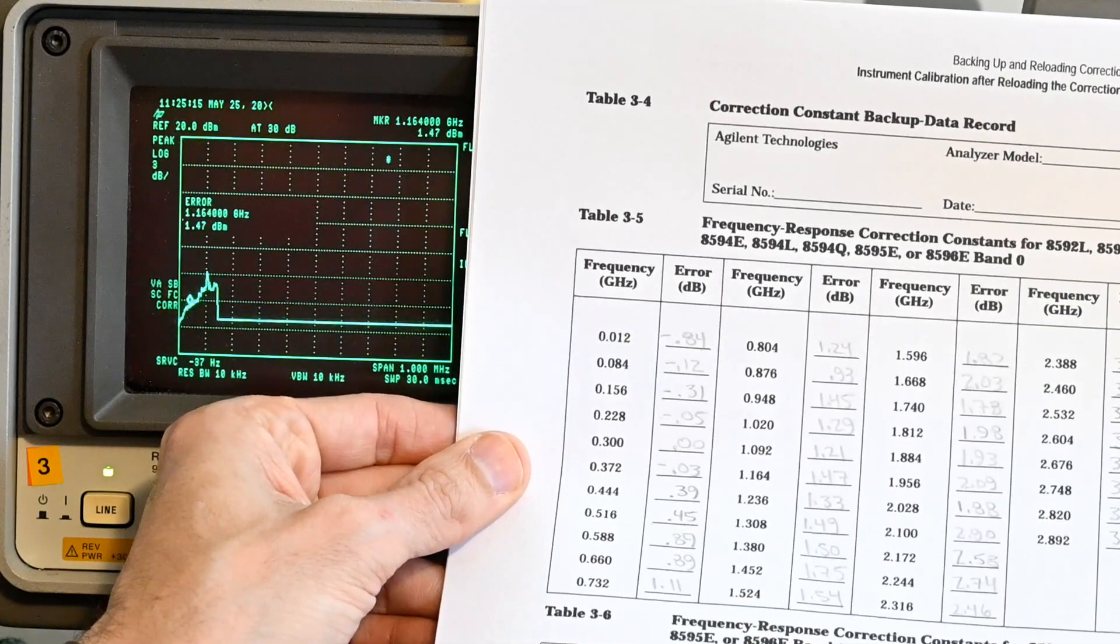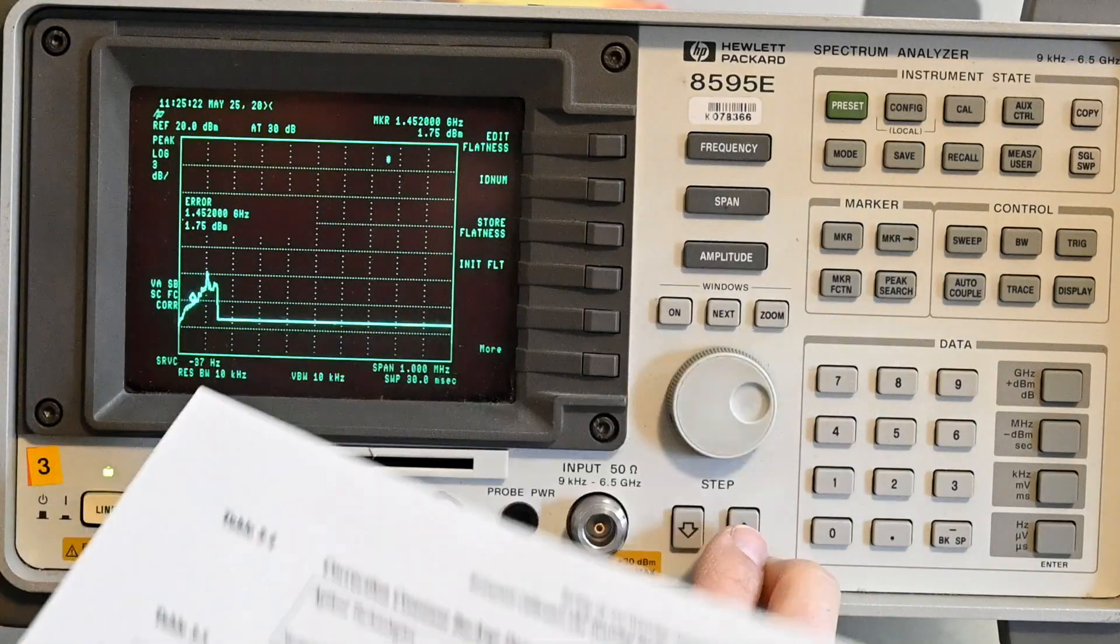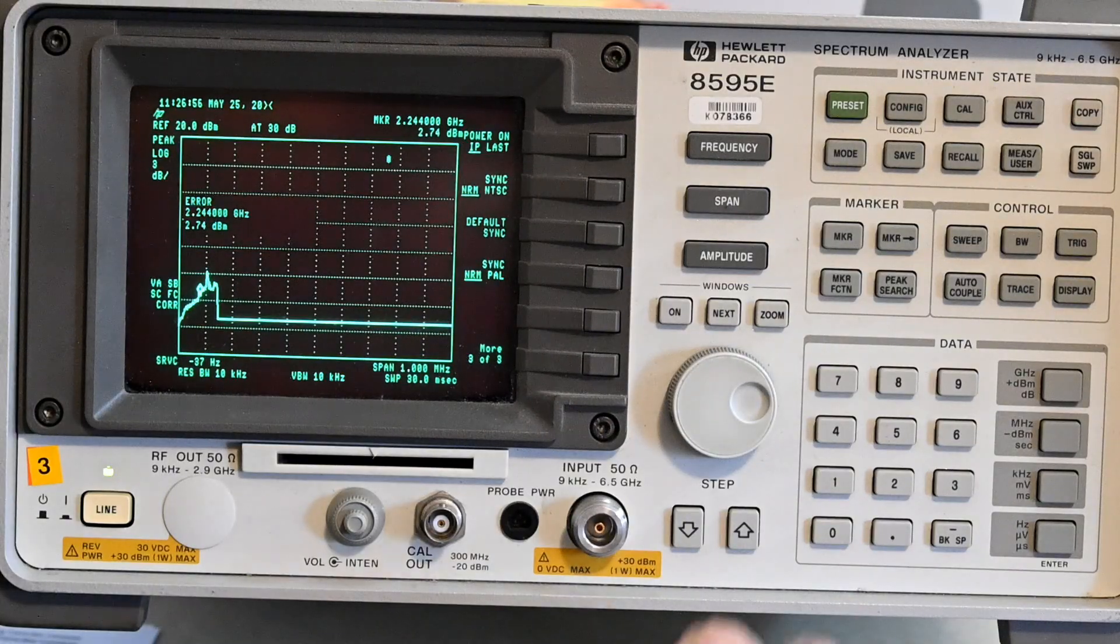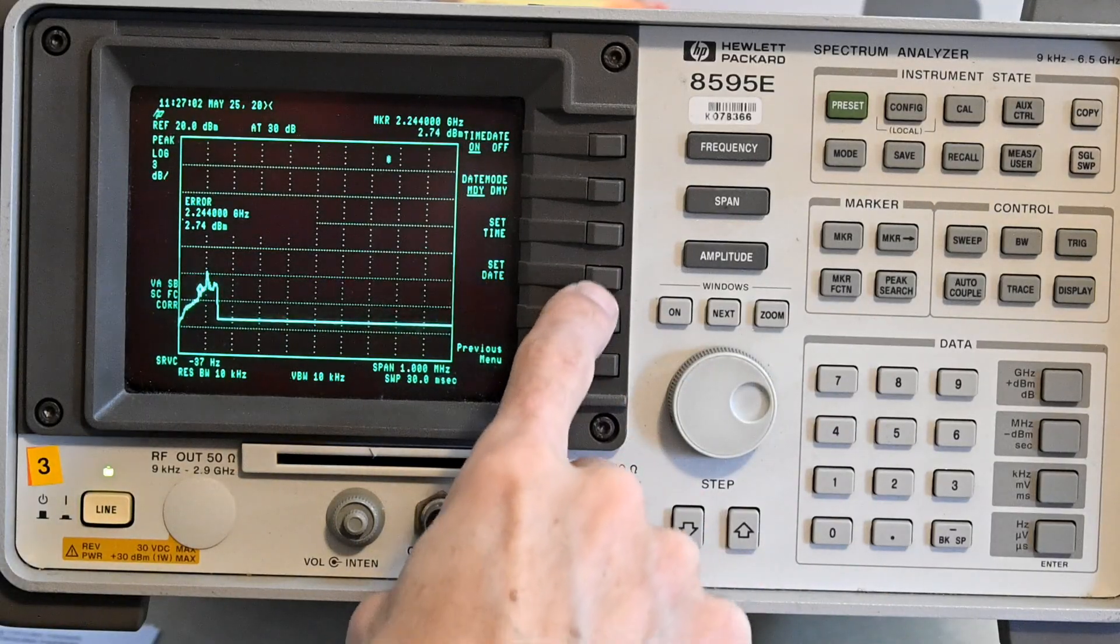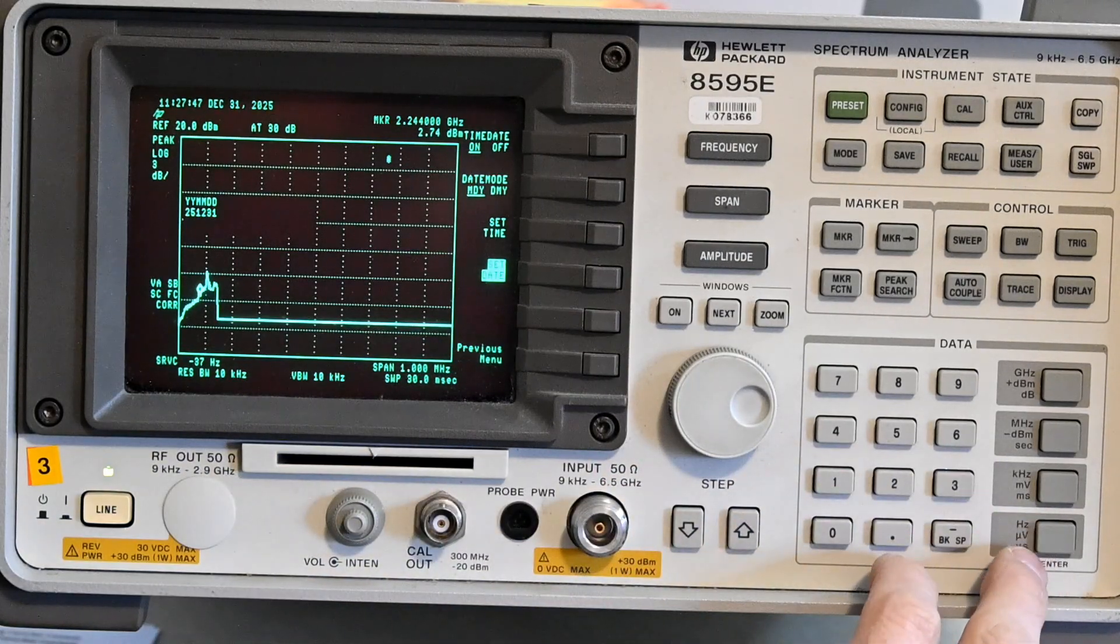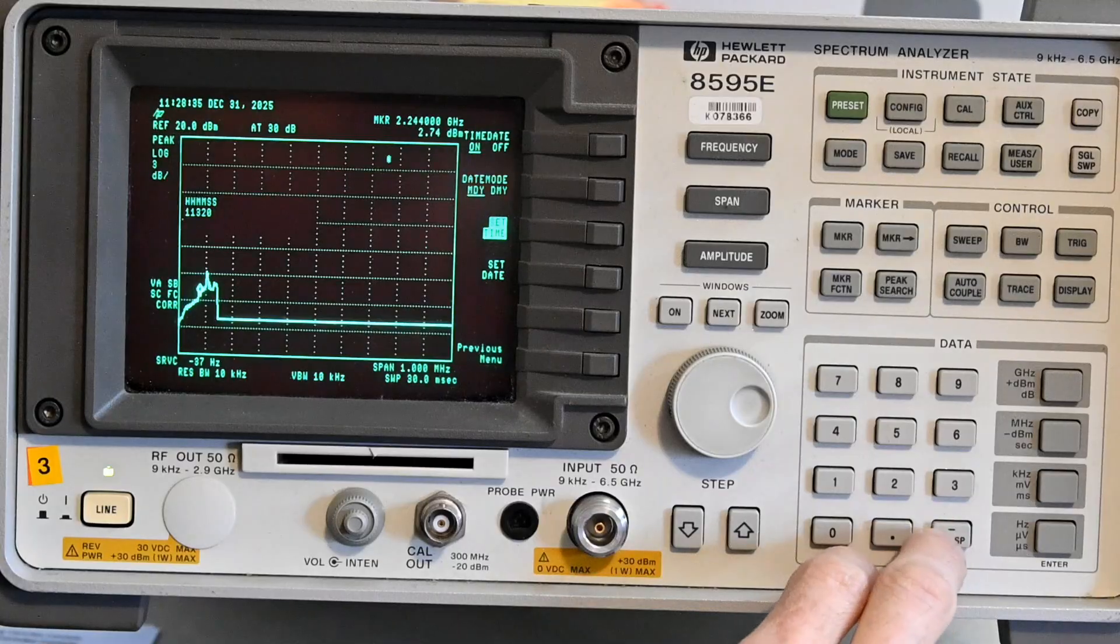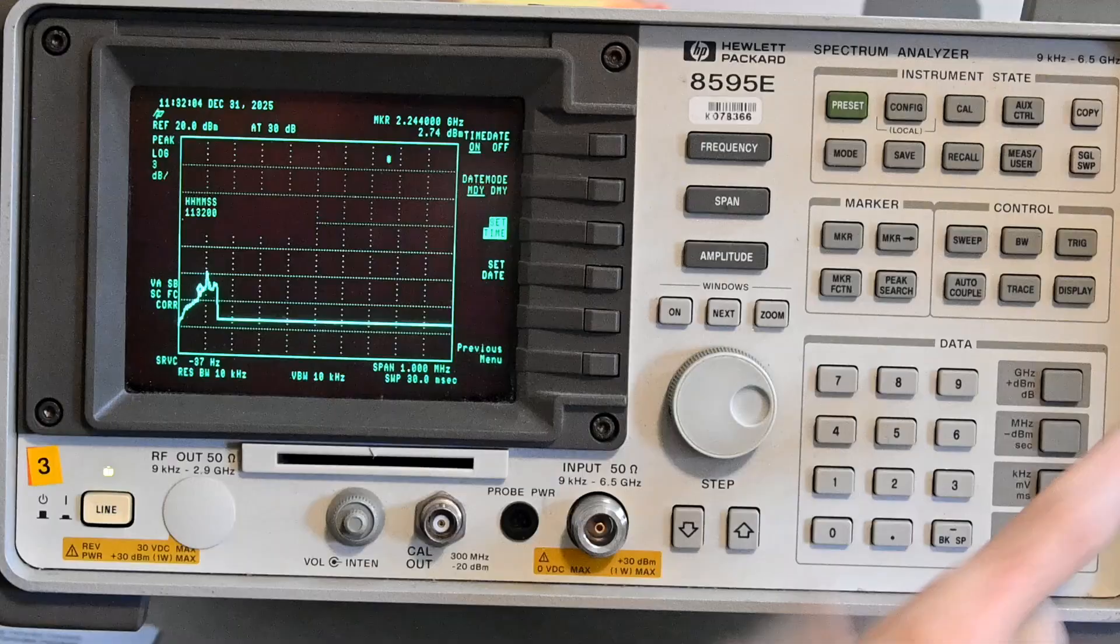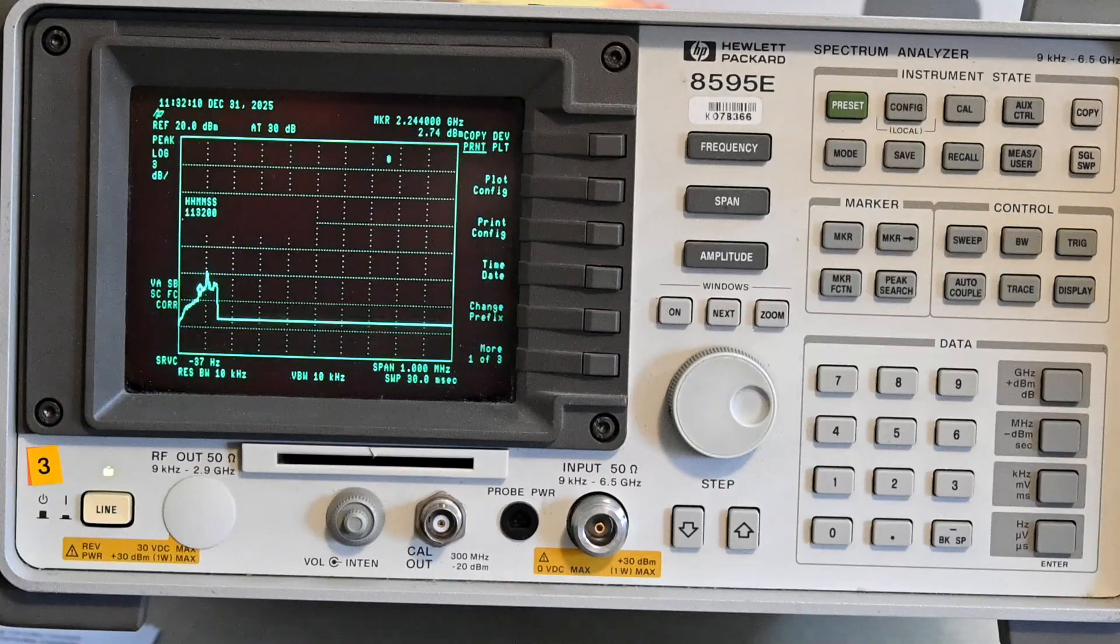One thing I'm confused about though is that the clock has gone out here. We no longer have the year there, but we do have the date and the time. Let's see if we can set that clock. We're going to go to config, time and date, set date. Use the Hz button as the enter, which is working, and now it's set. The date and time are set, which is great.